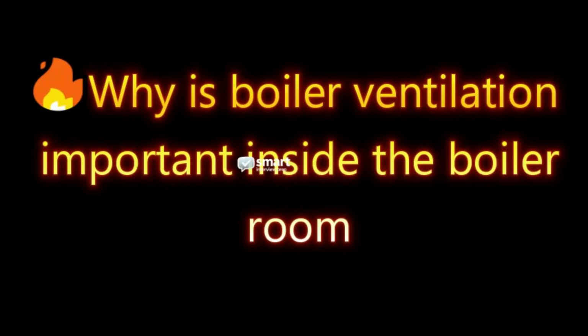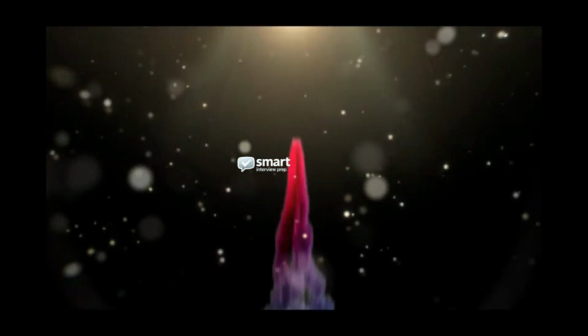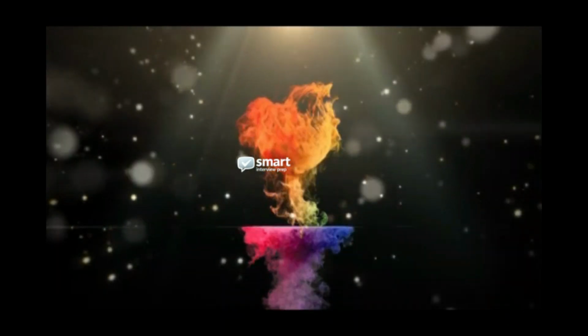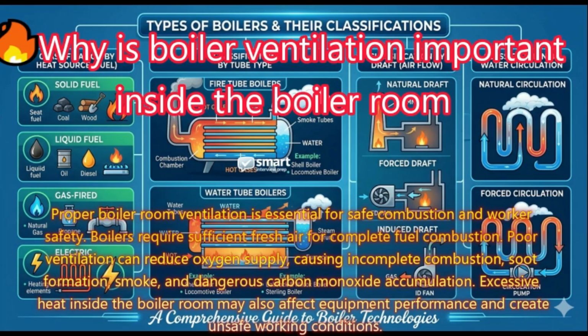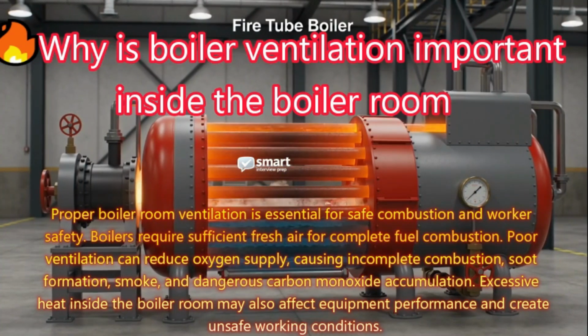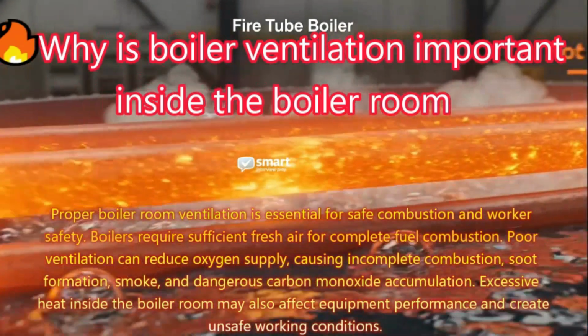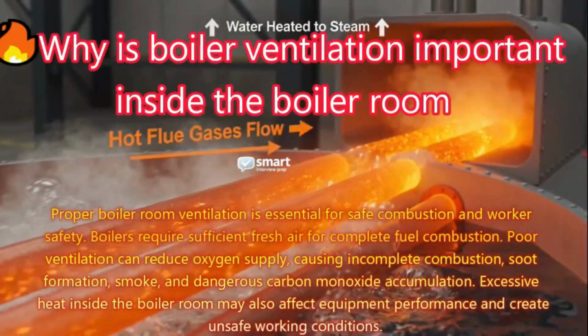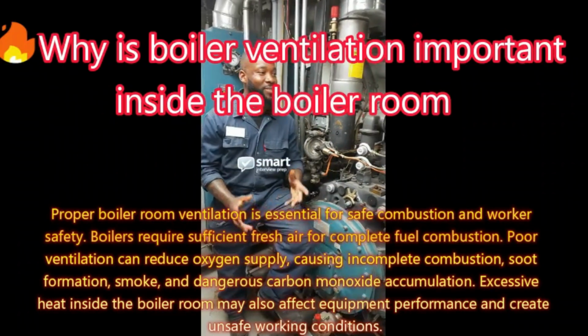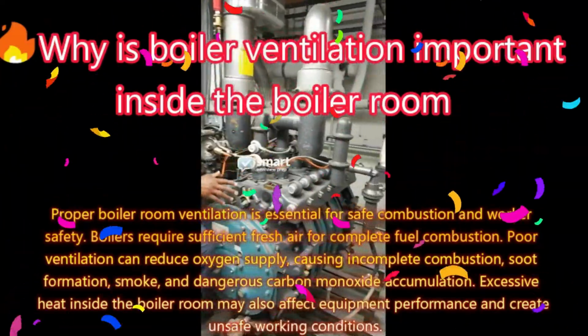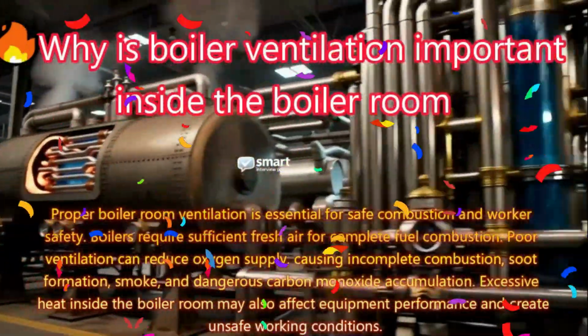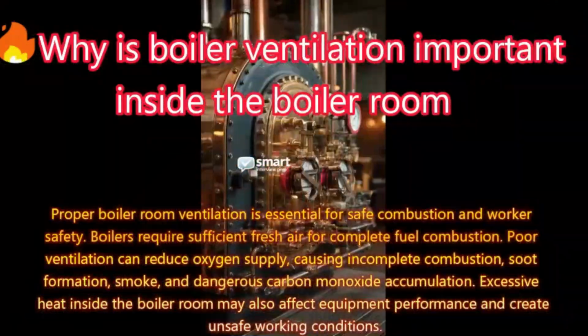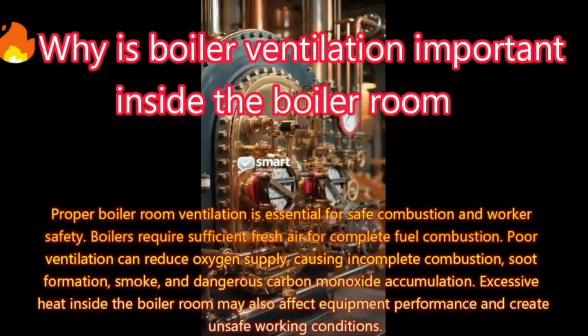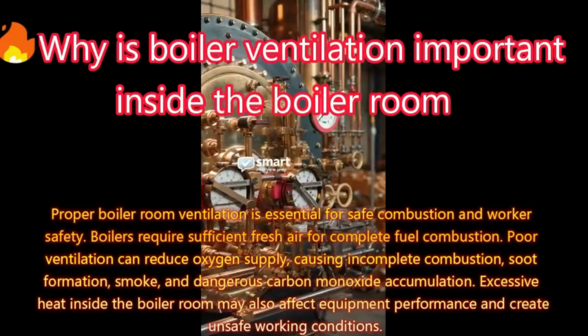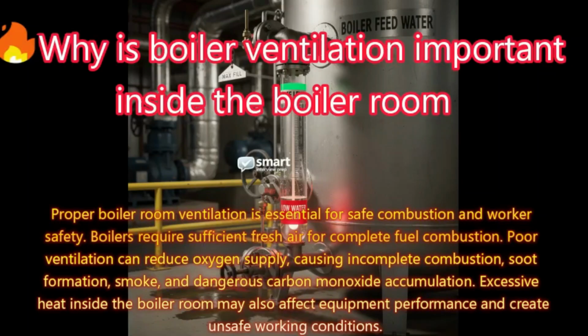Why is boiler ventilation important inside the boiler room? Answer: proper boiler room ventilation is essential for safe combustion and worker safety. Boilers require sufficient fresh air for complete fuel combustion. Poor ventilation can reduce oxygen supply, causing incomplete combustion, soot formation, smoke, and dangerous carbon monoxide accumulation. Excessive heat inside the boiler room may also affect equipment performance and create unsafe working conditions.